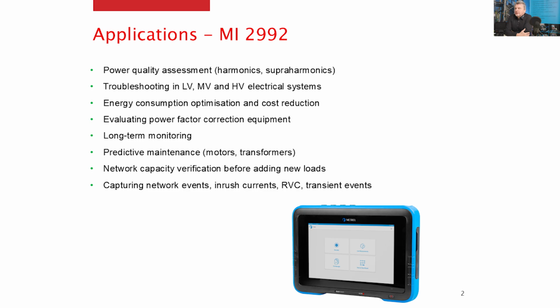If we check where this device could be used, we can see that it has a lot of capabilities regarding the harmonics and interharmonic measurement. It could measure up to the 63rd harmonics and interharmonics and supraharmonics from the range 2 kHz up to 15 kHz with 200 bins. So it's a perfect tool for analyzing power quality assessment. It could be connected to the low voltage, medium voltage, or high voltage electrical systems. And it's a perfect tool for energy consumption optimization and cost reduction measurement. Also, evaluating of power factor correction in equipment could be analyzed perfectly with 2992.